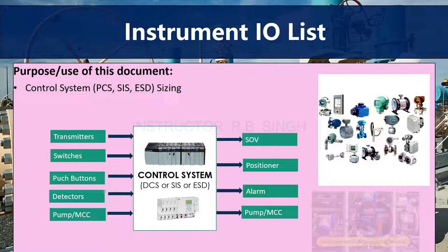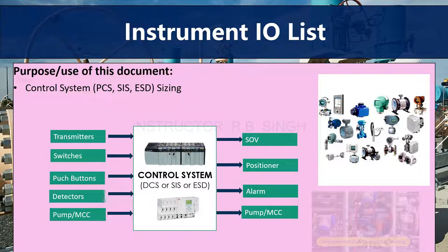As shown in the diagram below, some signals are coming in and some are going out of the control system. Transmitters — such as pressure transmitters, temperature transmitters, level transmitters, and flow transmitters — send signals to the control system; these signals are generally considered as Analog Input (AI). Switches such as pressure switches and limit switches send digital signals to the control system.